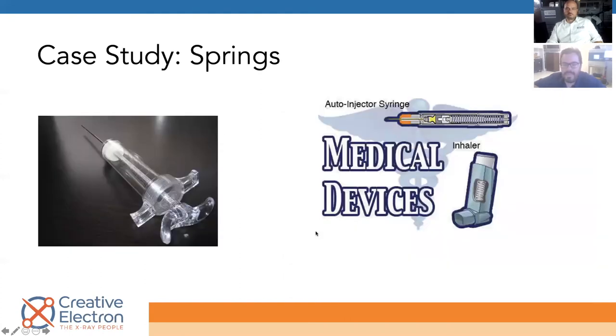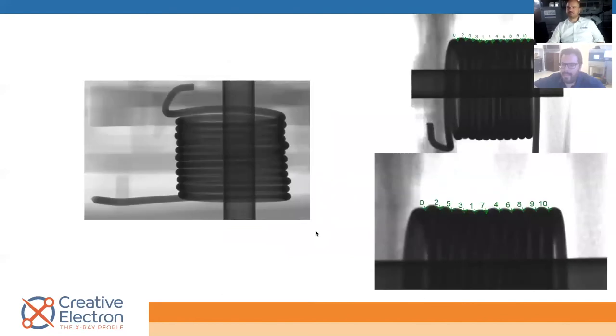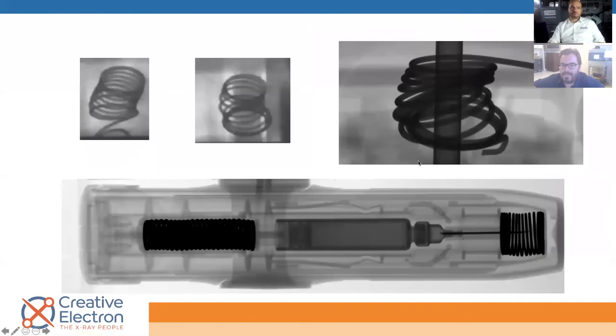Another big thing with medical devices is springs. We saw a few examples with the EpiPen. Here you can see a couple of images of springs, with annotations showing the coil counts — we're counting the coils each spring has. If we expect to see 11, but we count 9 or 12, that would fail. Here's another picture of an EpiPen showing springs, with examples of really bad springs — the ones on the left look like they're falling apart. Maybe they still work, maybe they were wound the opposite direction and just look bad, but you can't take the chance of having that in your product.